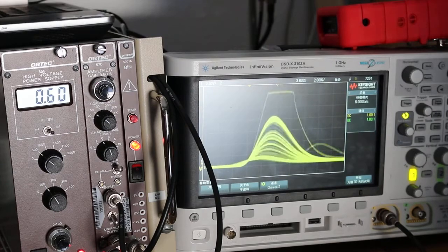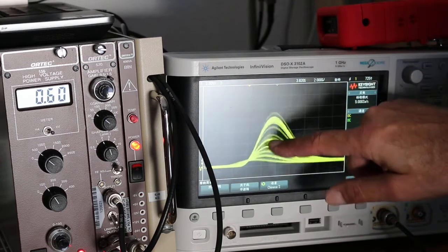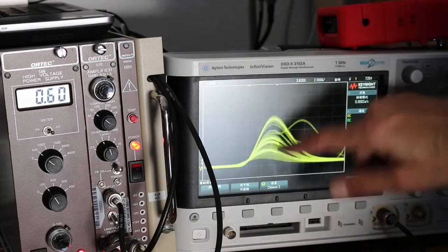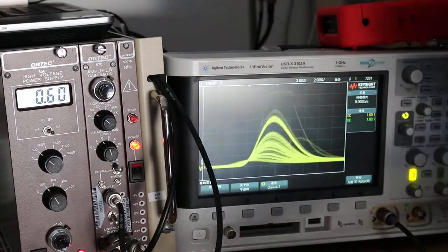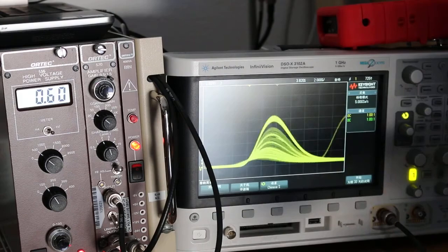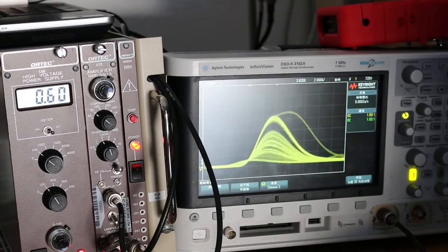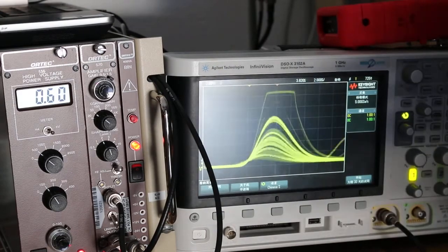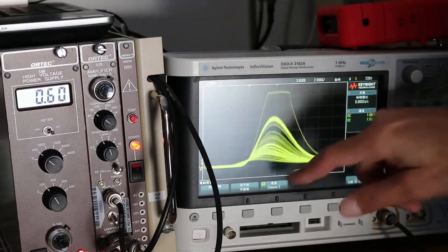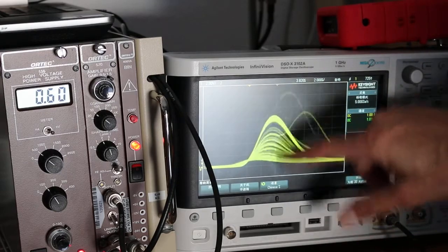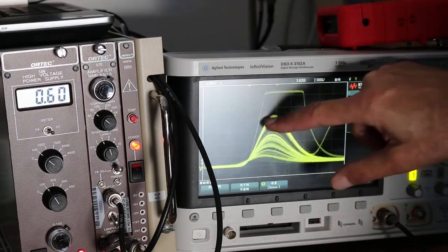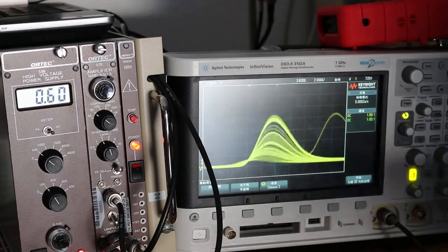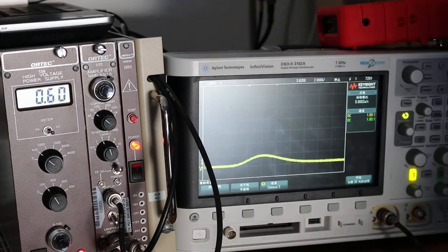You're always looking for a bunch of peaks that have a similar shape, but a whole bunch of differing amplitudes just coming in at all different times. So the reason why it flutters like this is just because of that. We don't know when the gamma ray of an energy is going to come in, but they all come in and fill the entire area below this primary peak in here.